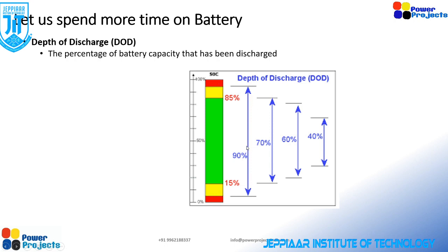Let's talk about this. The first one is 90% depth of discharge, meaning from 95% maximum SOC to 5% minimum SOC, so 95 minus 5 equals 90% depth of discharge. Similarly, if you set maximum SOC at 85% and minimum SOC at 15%, then depth of discharge is 70%, and so on for 60 and 40.